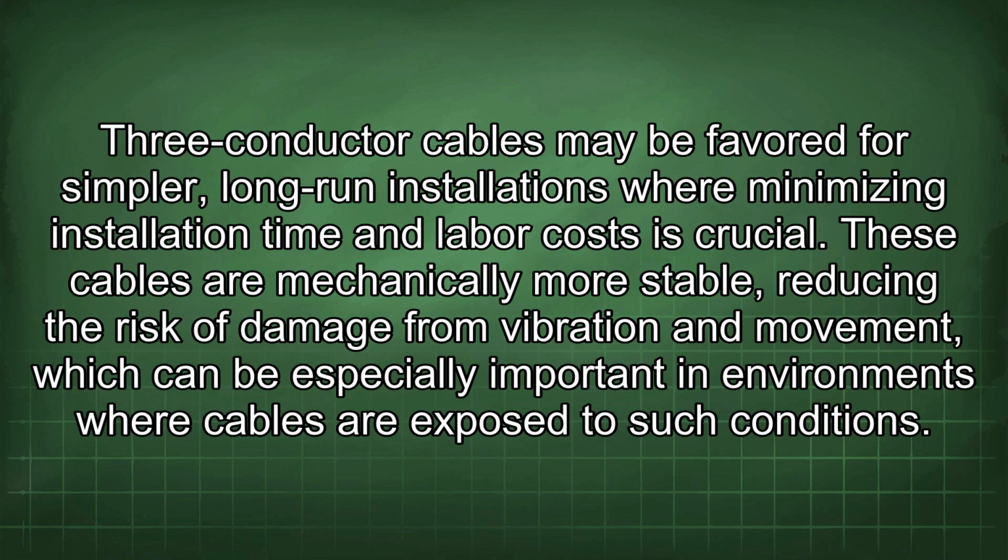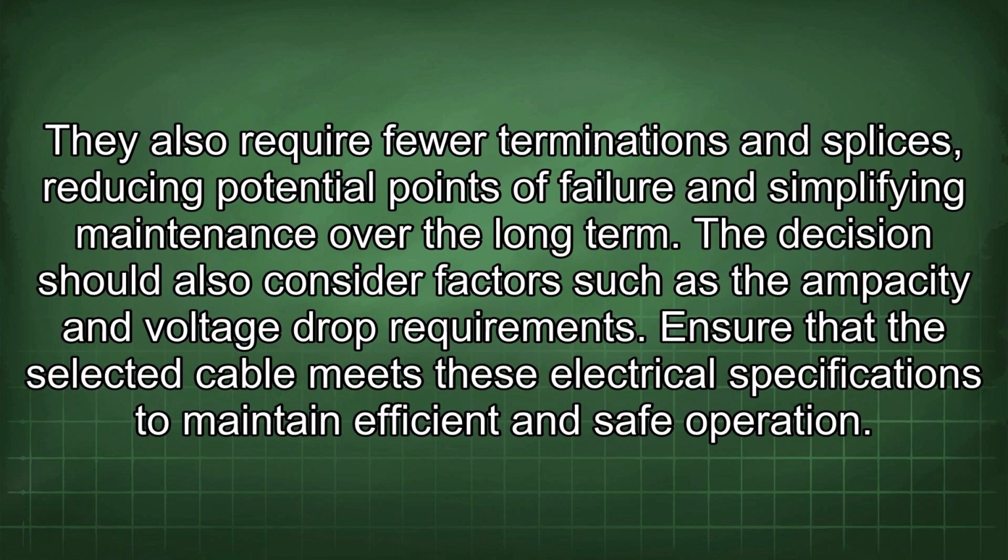Three-conductor cables may be favored for simpler, long-run installations where minimizing installation time and labor cost is crucial. These cables are mechanically more stable, reducing the risk of damage from vibration and movement, which can be especially important in environments where cables are exposed to such conditions. They also require fewer terminations and splices, reducing potential points of failure and simplifying maintenance over the long term.